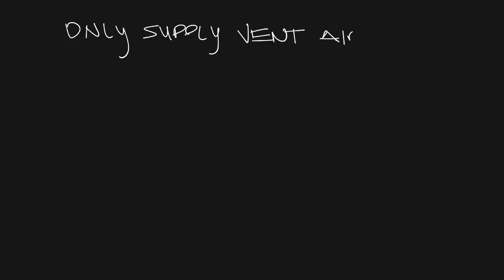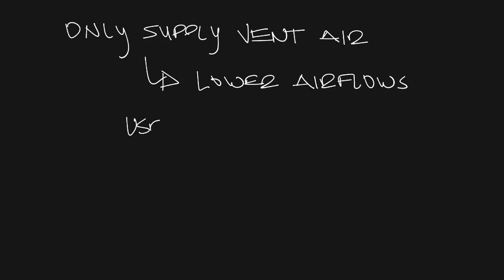Since the DOAS system is only handling the ventilation air, you use less air than you would in a typical VAV system. You would also want to use a parallel sensible cooling system to handle the sensible load in the space.